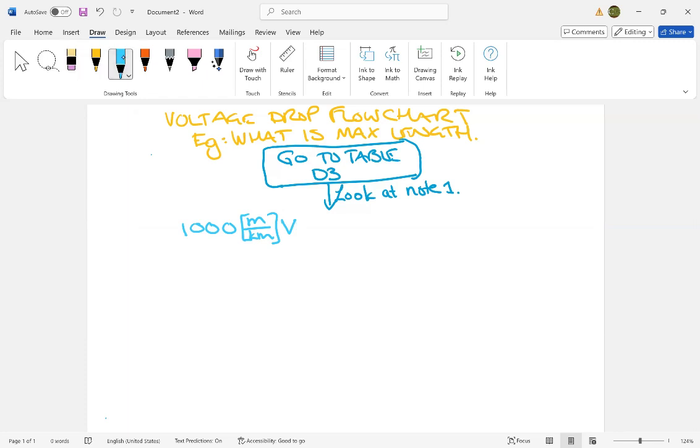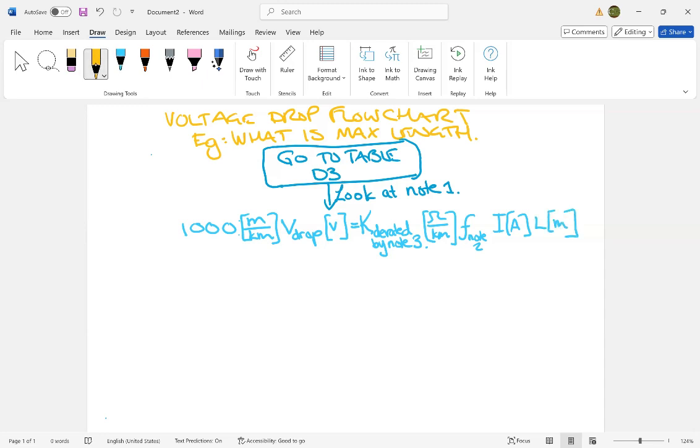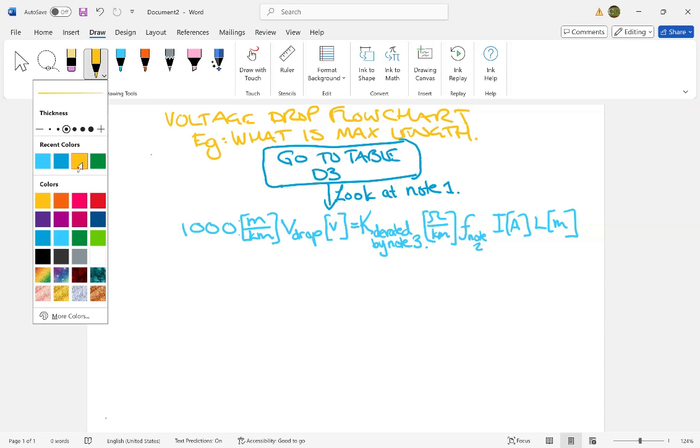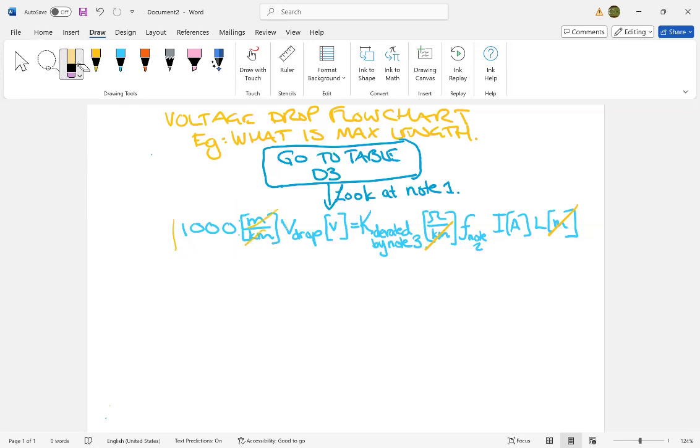So you can look at my other videos if you want an explanation, but 1,000 times meters per kilometer takes into account, it changes your units properly. So 1,000 times voltage drop in volts is equal to K, but that has to be derated, so I like to put subscript to remind me that it's derated by note 3, a factor that is described in note 3, and that has the units of ohms per kilometer, and then that's multiplied by a little factor F that is described in note 2 of table D3. And then we multiply that by the length, which is in meters, so you see here that our units are in kilometers here and meters here, and this is just a conversion between kilometers to meters so that our formula works out, and all of our units work out.